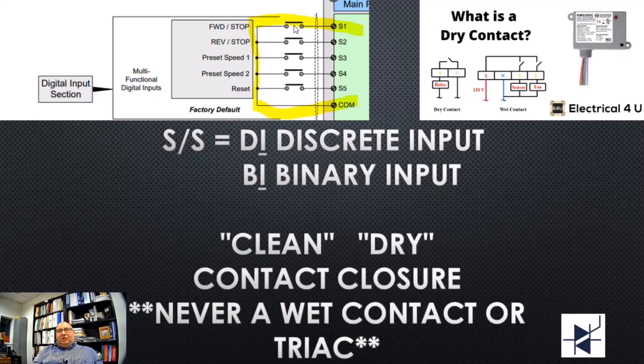So we could do it with a RIB, we could do it with a cube. We cannot share that switching with anything else, okay? And it cannot be what's known as a wet contact. Here's a wet contact. Ruben does a great job talking about this. You need to understand the theory of a wet contact for the STAR review. A wet contact is something that shares multiple relays, usually on the common side or the neutral side of the switching. And it cannot be a triac either, okay?